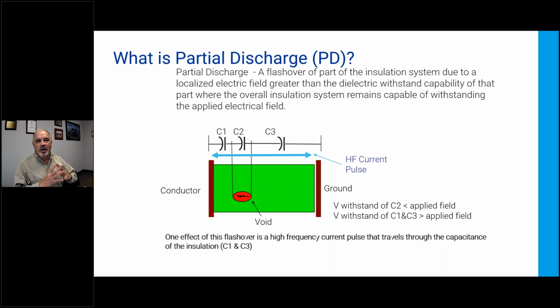So what is partial discharge? We all have our own little definition. The Wikipedia definition is it's a flashover of part of the insulation system due to a localized field that's greater than the withstand capability. What that means is I don't have a complete flashover from line to ground, or line to neutral, or line to line, but I do have it over part of the insulation that might go line to line or line to ground. And that little partial discharge is what's going to cause us problems.